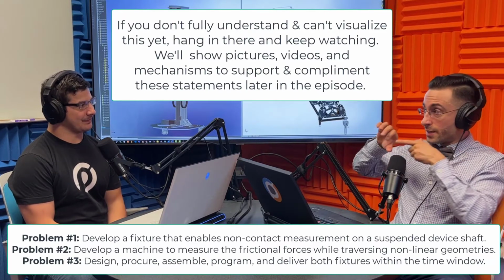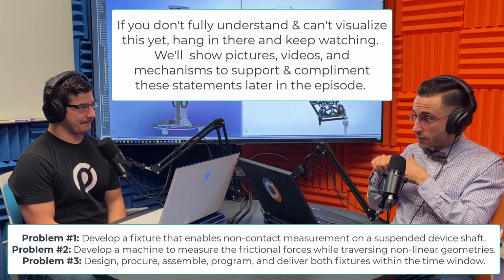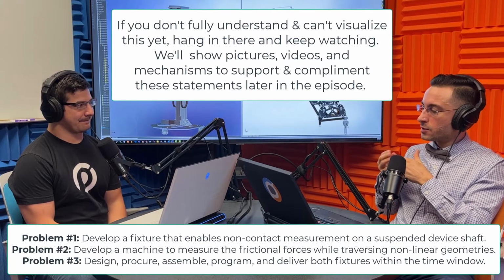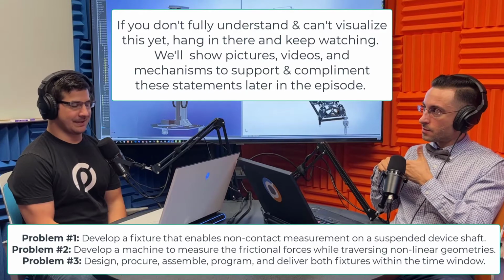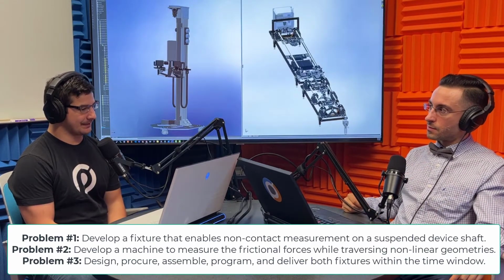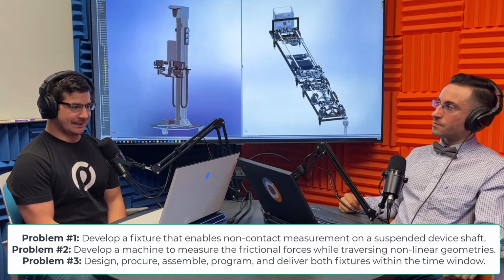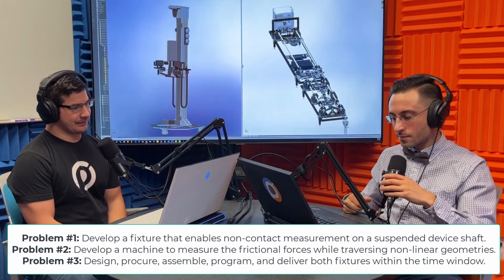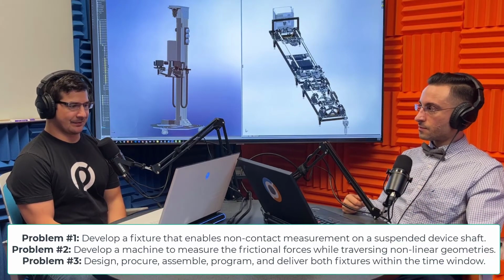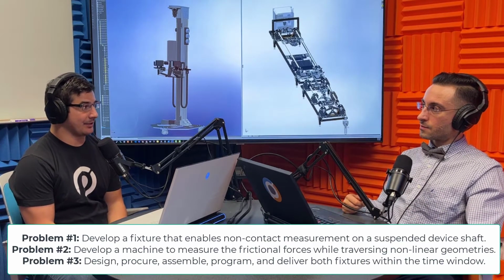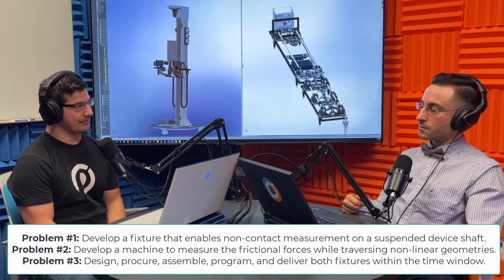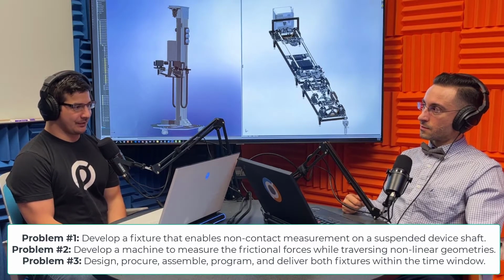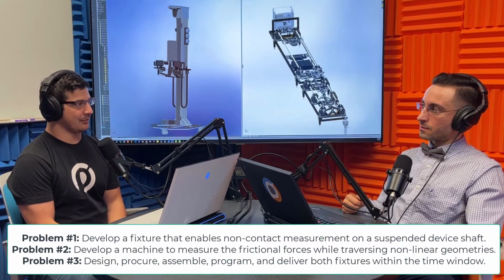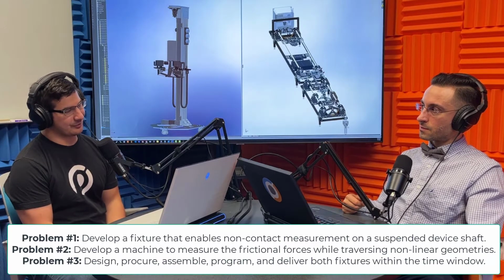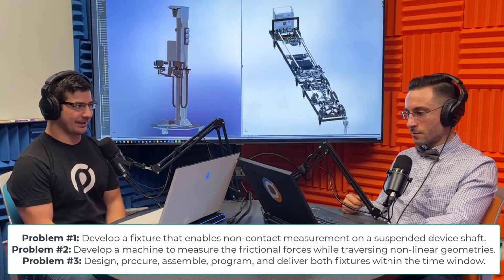So there's a catheter going into the veins. We don't want to perforate the veins. So what kind of testing do we need to do so that that doesn't happen? One test that we do is what's called an insertion force test. And we can set speeds and forces and take measurements on that friction coefficient along its path of travel. So from that, you can either optimize or set boundary limits for how the device should perform, and then you can catch low-performing devices and quality problems down the line.